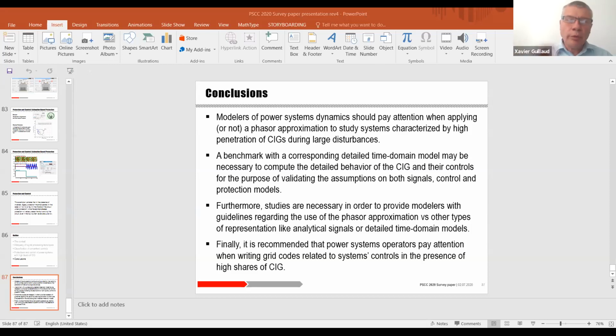There are two parts to the answer. Either you have the MMC — the connection of the MMC to the grid is extremely simple due to the MMC topology, there is no filter, so it's just a matter of current limitation. But if we design the MMC for a given nominal power, then you design the current limitation, and you will have in fact the same current limitation either for grid following control or for grid forming. So the design will be the same, in my opinion.